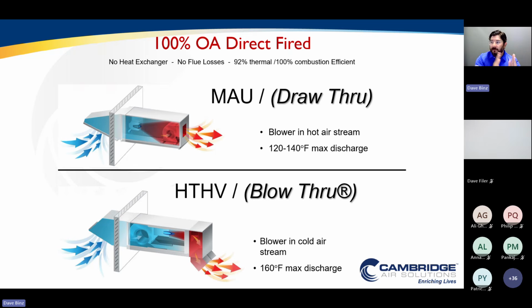Because of that, I'm typically limited in discharge temperature. I don't want to go higher than really 120 degrees, because now my motors and bearings' life expectancy and half-life is going to drop significantly. If you talk to any motor manufacturer, they'll tell you for every 10 degrees above 104 Fahrenheit, they lose about half their life. So when you look at 135-degree discharge temperatures in these makeup air units that I sometimes see from other manufacturers, those motors are getting burnt out every 5 years. Still no heat exchanger, no flue losses.